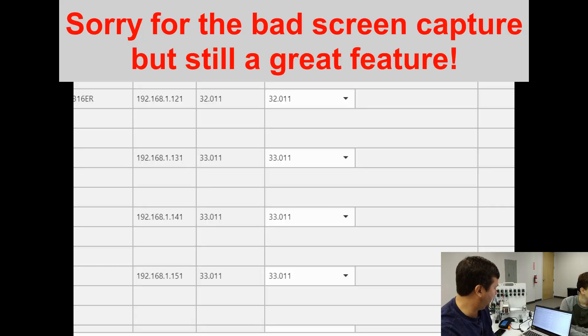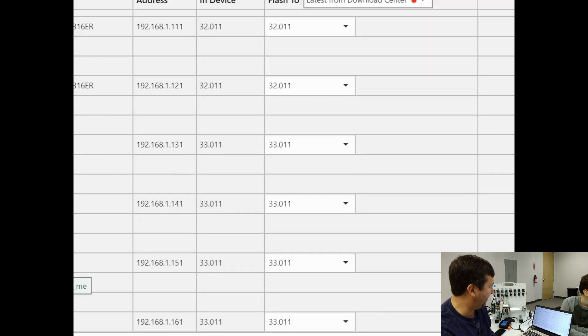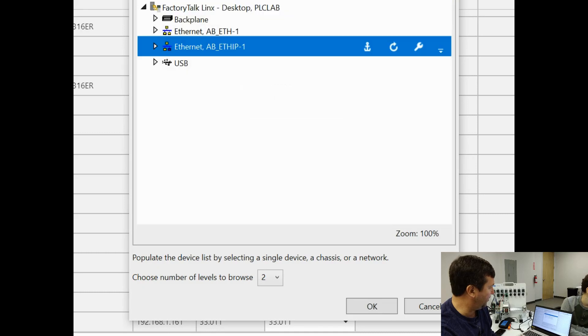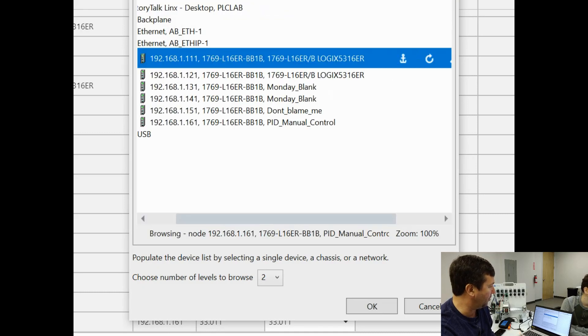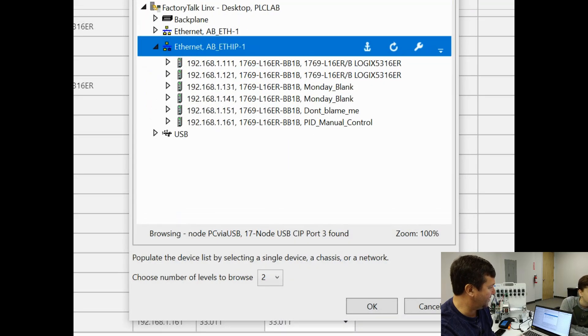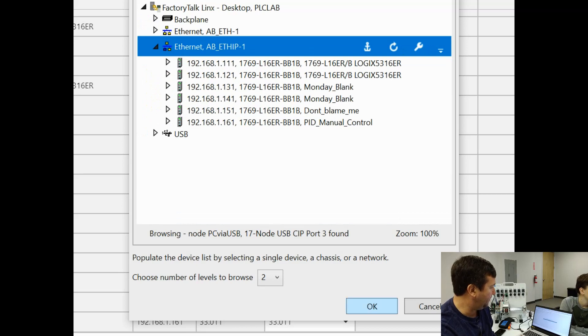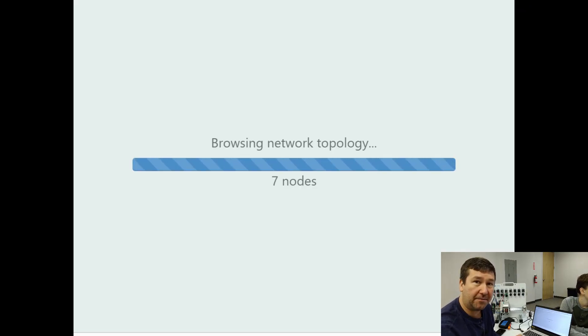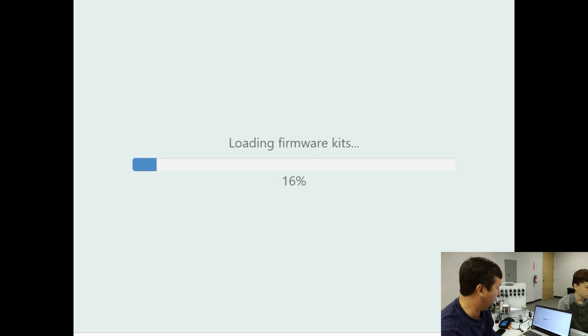So we have six of the 1769 L16 ERs. Now first, how did I get there? I clicked the browse button here, and typically you would drill on down and select a PLC that you want to work with, but we can actually go and just select our driver, the particular one, and then we're going to click OK, and it's going to browse and find all of the nodes that are out there on Ethernet IP.